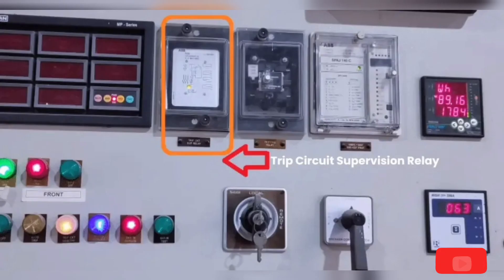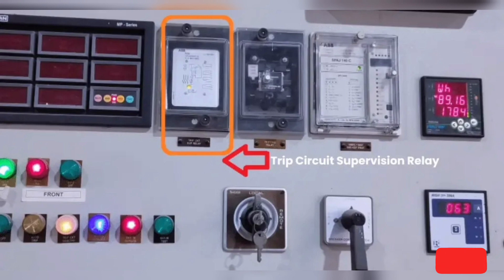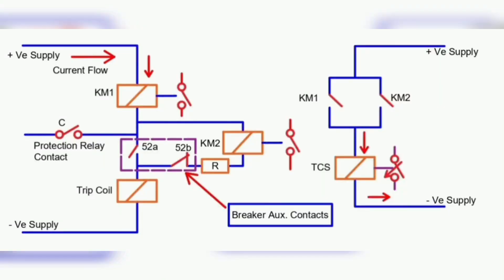In order to perform the closing, opening, and tripping operation, a breaker has two coils: the closing coil and the tripping coil. The tripping of the breaker in the event of a fault is a must to safeguard the electrical network and the equipment connected to the outgoing side of the breaker. The healthiness of the tripping circuit should always be intact. The tripping circuit mainly has a 110V DC tripping coil, a 110V DC source, and the connecting wires to the tripping coil.